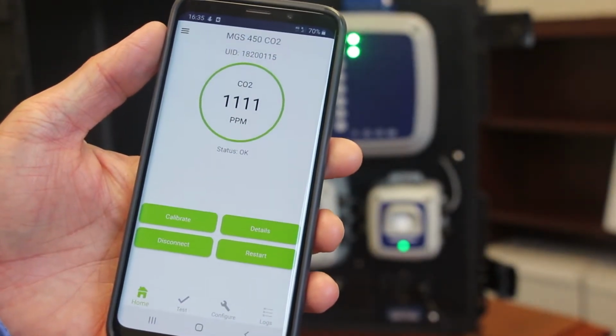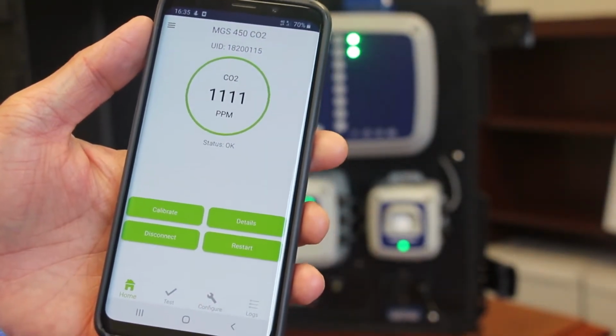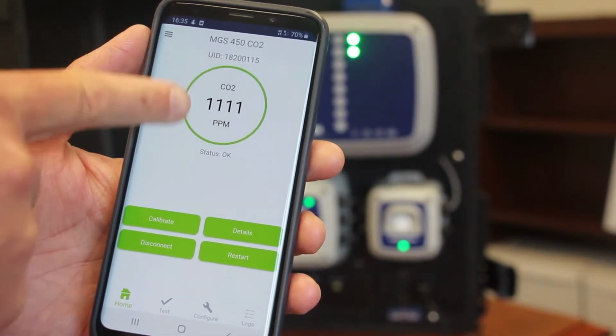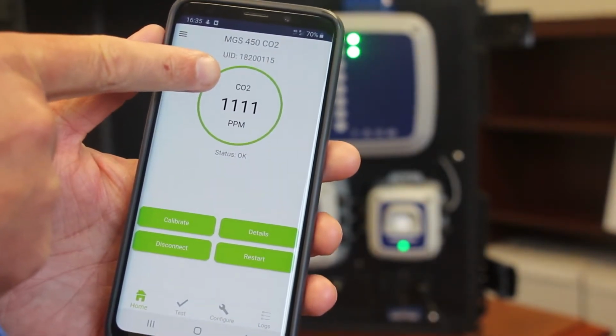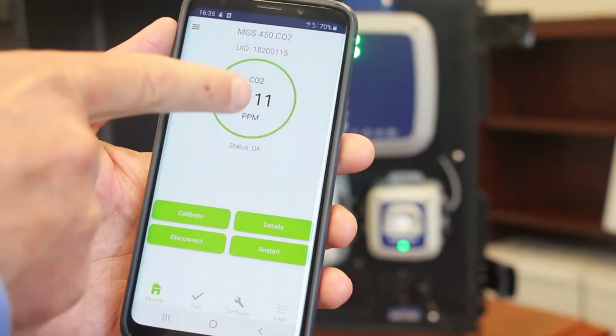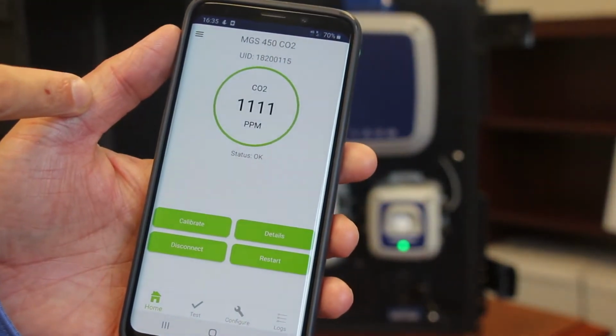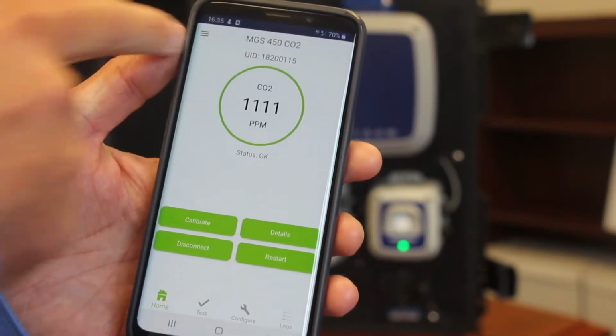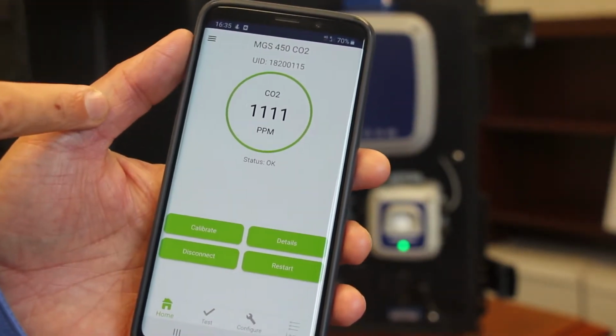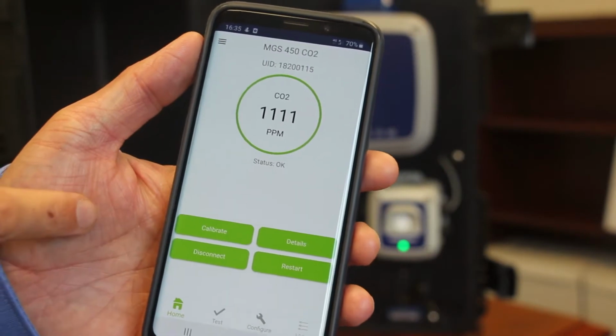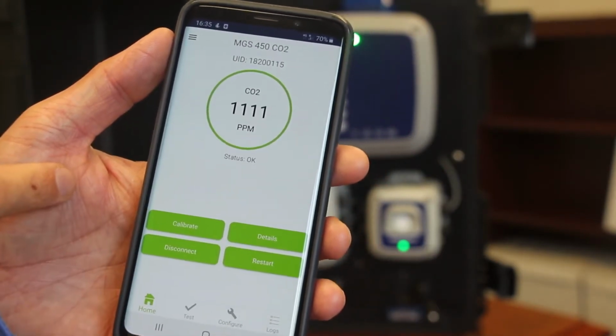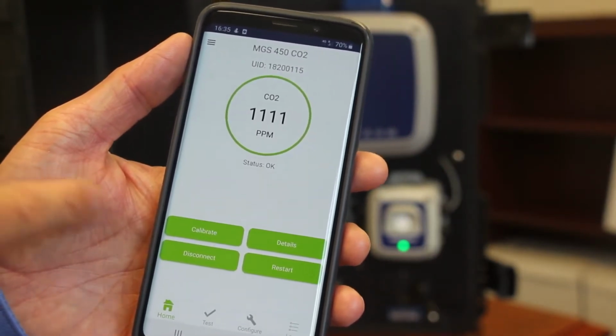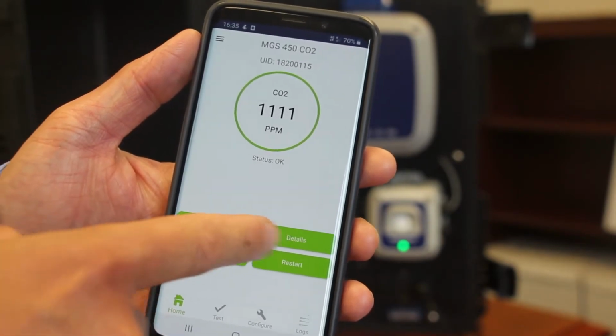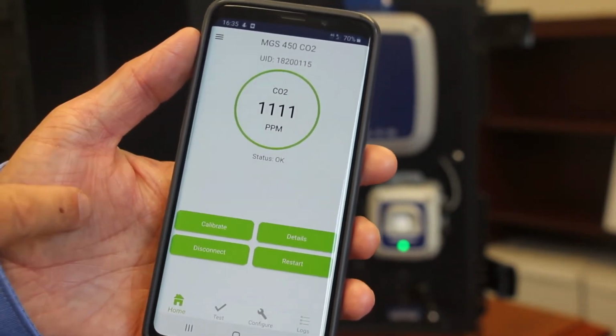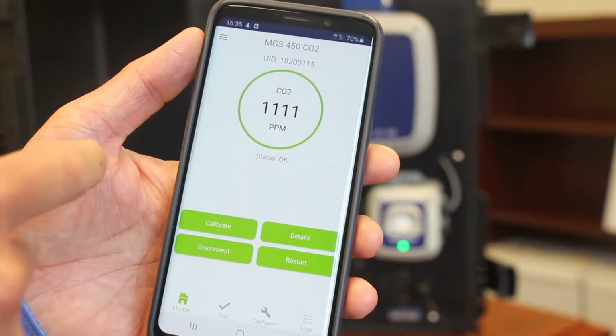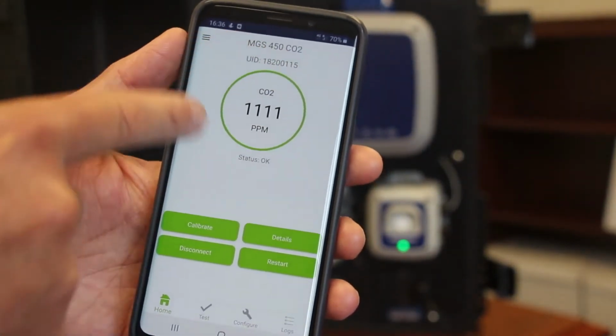Okay, so once you're connected, you'll see this opening screen here. In the center here, we'll have the refrigerant gas that it's connected to on the detector. A real-time indication of the parts per million reading. You'll have the unit across the top here and one of the serial numbers. And then there are a number of different items that you can use on here, and we'll go through each of these step by step. So you have a calibration button, a details button, you can disconnect from the unit, and you can restart the unit as well.